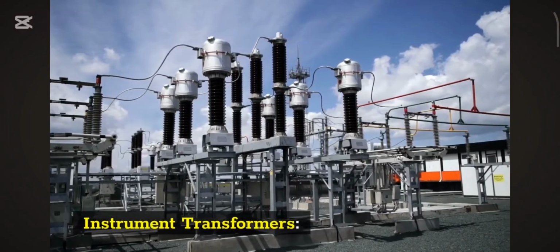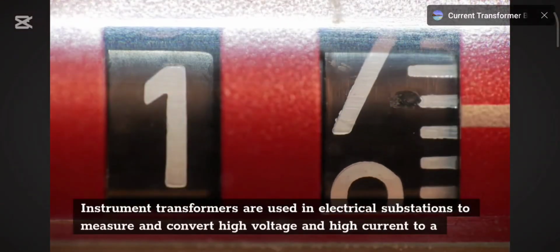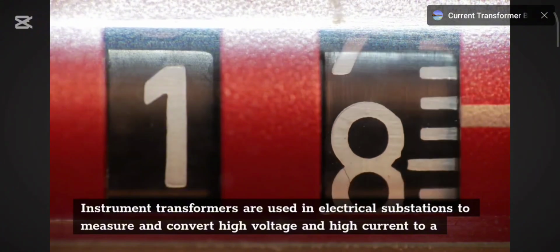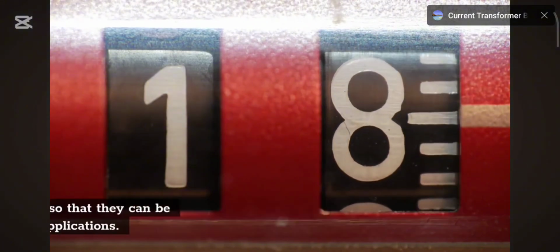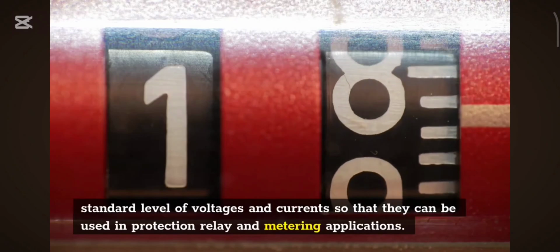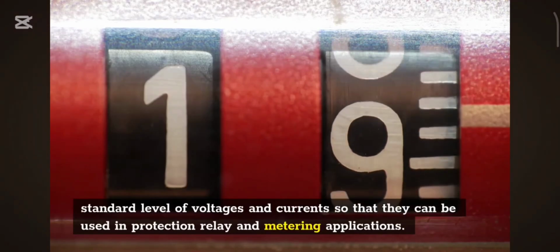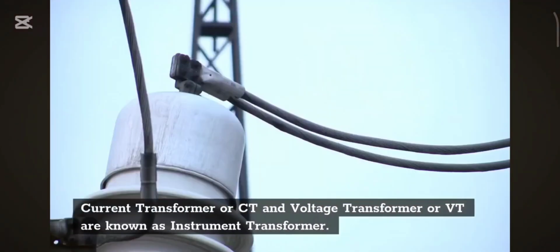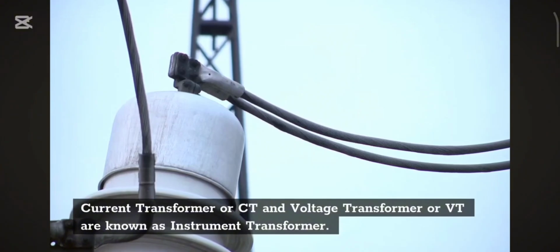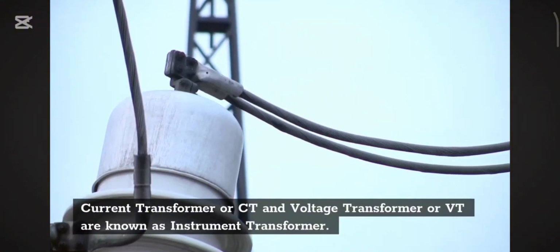Instrument transformers. Instrument transformers are used in electrical substations to measure and convert high voltage and high current to a standard level of voltages and currents so that they can be used in protection relay and metering applications. Current transformer or CT and voltage transformer or VT are known as instrument transformers.